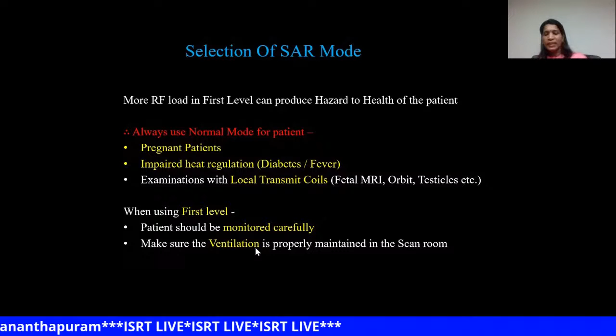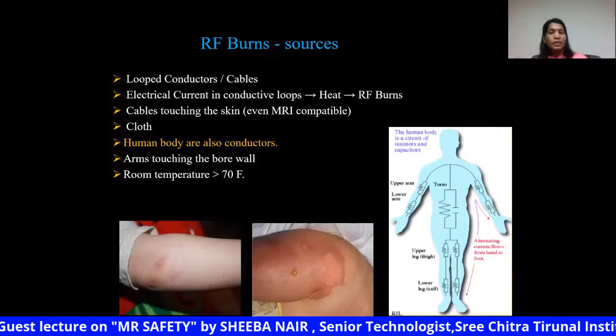These are the sources of RF burns in an MR system. Any looped conductors or cables: the RF field is a rotating magnetic field which will induce current and can produce heat. Then there are cables touching the patient's skin. If the cloth has some conducting material, it can produce burns. The human body is a good conductor. If the human body forms a closed circuit, that is by crossing the patient's hands, or crossing the toes, or touching the thighs, a large loop will be formed.